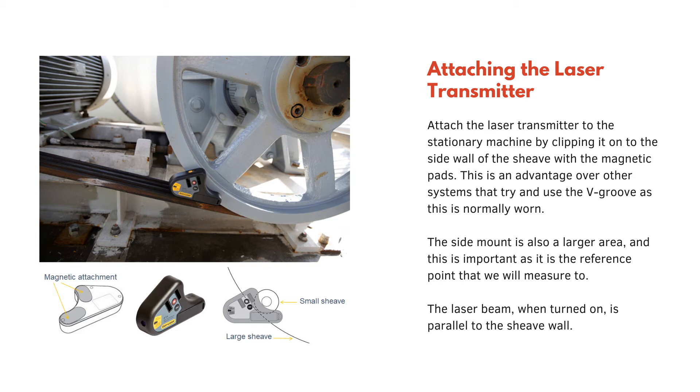Attaching the laser transmitter: attach the laser transmitter to the stationary machine by clipping it onto the side wall of the sheave with the magnetic pads. This is an advantage over other systems that try and use the V-groove, as the groove is normally worn. The side mount is also a larger area, which is important as it's the reference point that we will measure to. The laser beam when turned on is parallel to the sheave wall.